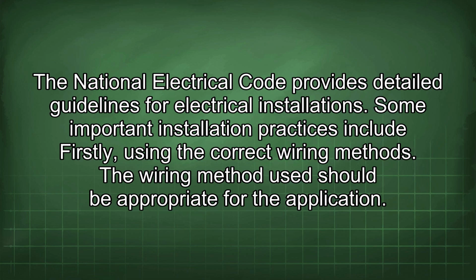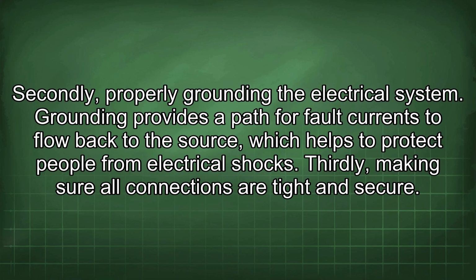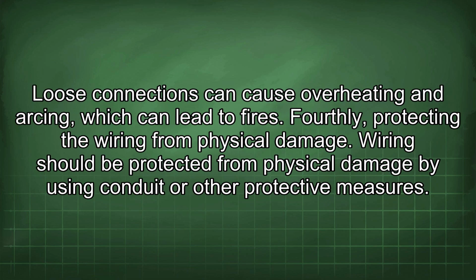Some important installation practices include, firstly, using the correct wiring methods. The wiring method used should be appropriate for the application. Secondly, properly grounding the electrical system. Grounding provides a path for fault currents to flow back to the source, which helps to protect people from electrical shocks. Thirdly, making sure all connections are tight and secure. Loose connections can cause overheating and arcing, which can lead to fires. Fourthly, protecting the wiring from physical damage. Wiring should be protected from physical damage by using conduit or other protective measures.